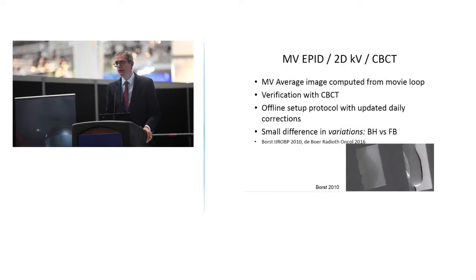We can also use megavoltage imaging, and there's nice papers out there on using CINE EPID where you can use a movie loop. In one case they take the average image and then have an offline setup protocol. So they're not using it real time, but then they're using this information and modifying the setup for subsequent days. They actually looked at the variations for free breathing and for breath hold patients and saw that the variations were about the same, suggesting that the precision of breath hold treatments were roughly similar to conventional free breathing treatments.